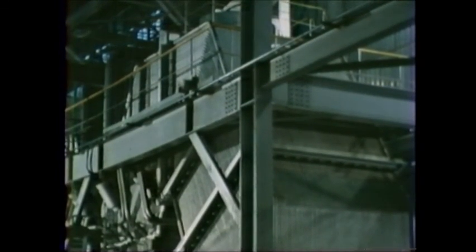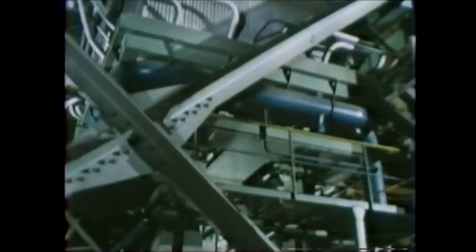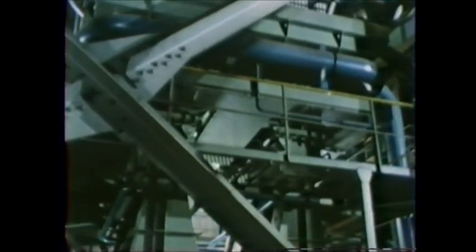Since gas cooling and dust collecting are accomplished with the gas in an unburnt state, the gas volume to be handled is less than 1/4 that in conventional processes. This radically reduces the sizes of the cooler and dust collectors. The gas leaving the cooler at about 1000 degrees centigrade or 1800 degrees Fahrenheit is further quenched and cleaned as it passes through the quencher and venturi.